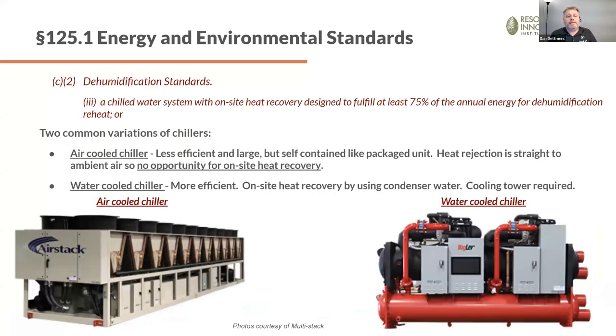Another option out there is a chilled water system with on-site heat recovery designed to fulfill at least 75% of the annual energy for dehumidification. Why did I read that? Well, a chilled water system is a chiller, something that produces cold water. That cold water goes to a coil that does the cooling of the space, that does your dehumidification. But a lot of times we've got to heat the air back up.